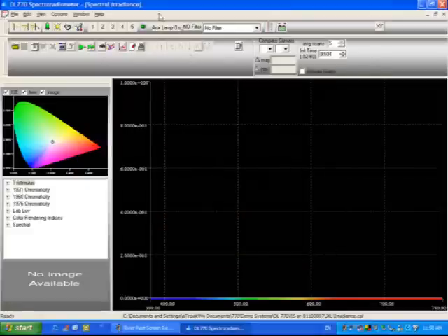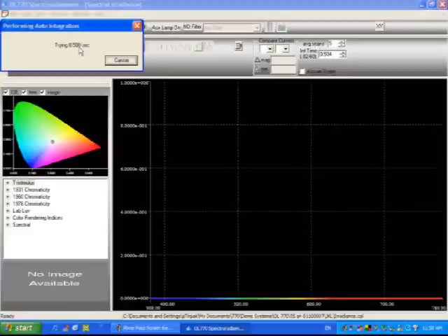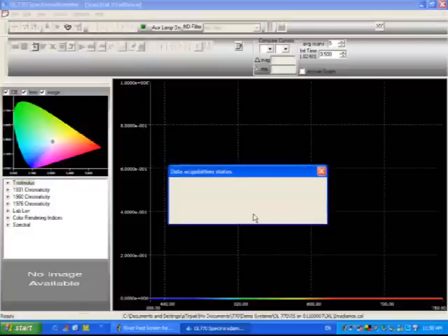Again, I'm going to use the auxiliary lamp to measure. It's again the same tungsten source we used before, an average five scans. So I'll just click the play button. It's going to take your five dark scans and it's going to take five measurement scans.